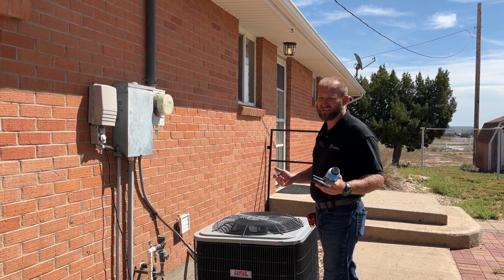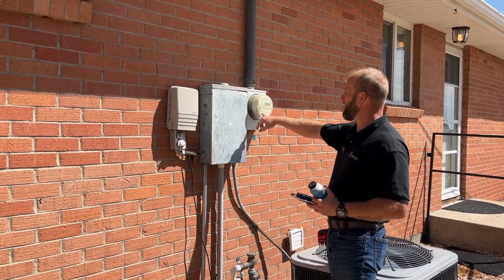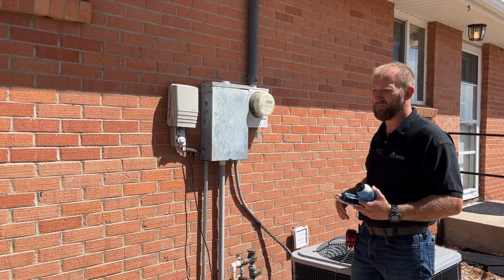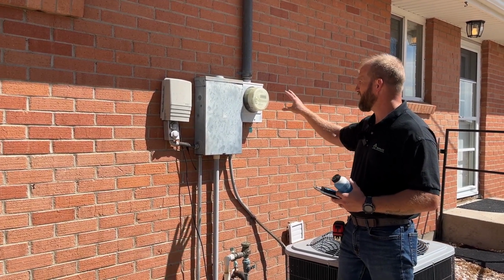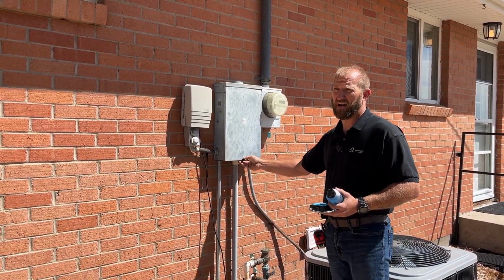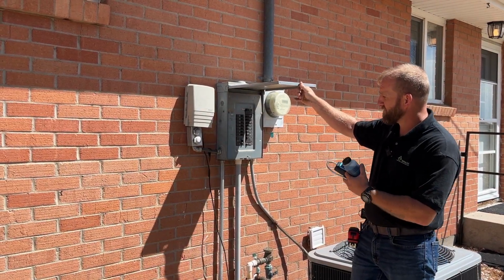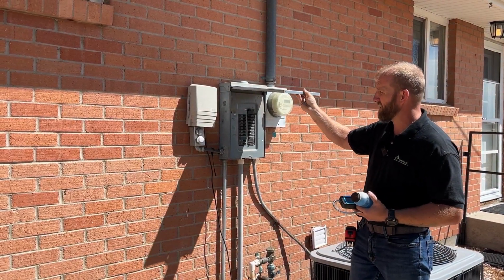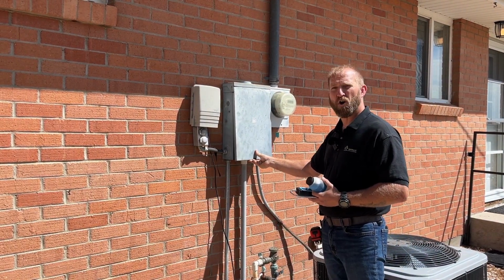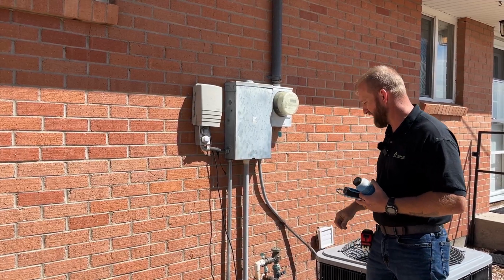Okay, so once we've finished the gas meter, we can see on the electrical meter who the power company is. If we're not already sure who that is, we can take a picture of that. In certain instances, if we're going to be doing or recommending upgrades, we might look at the panel and see if the panel is completely full, what the rating on the panel is. That can help us know scope of work if we're doing bids for the client.